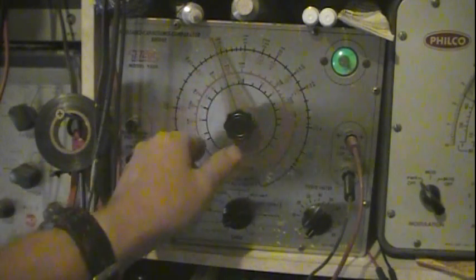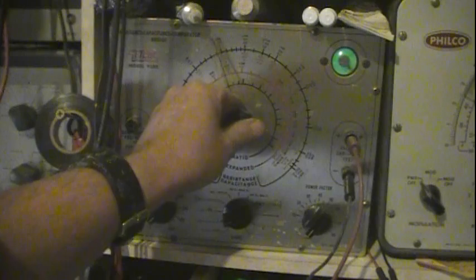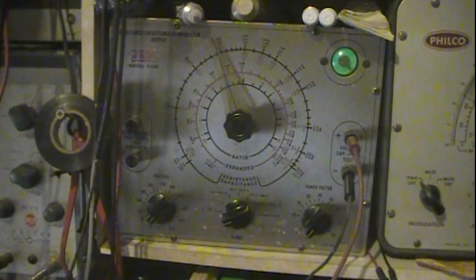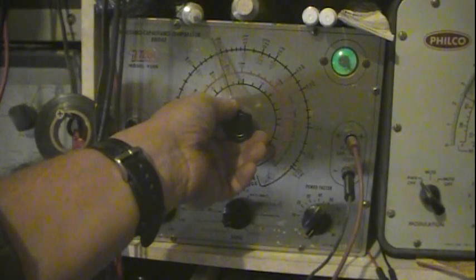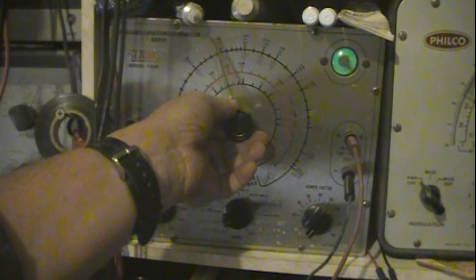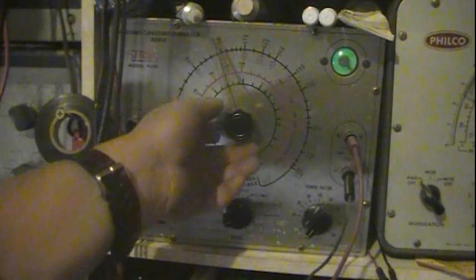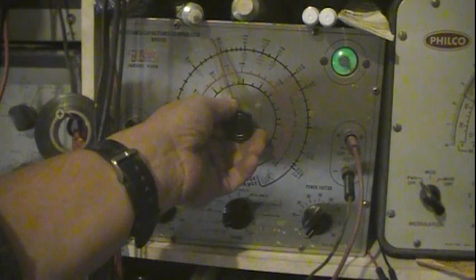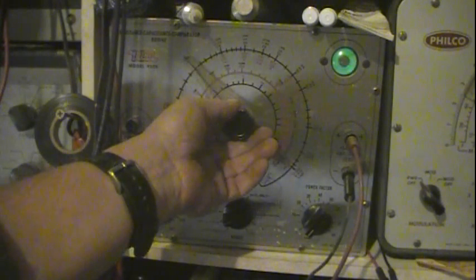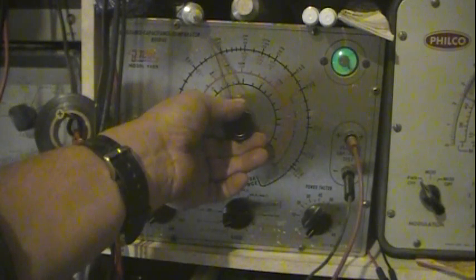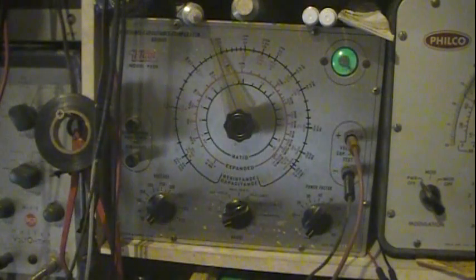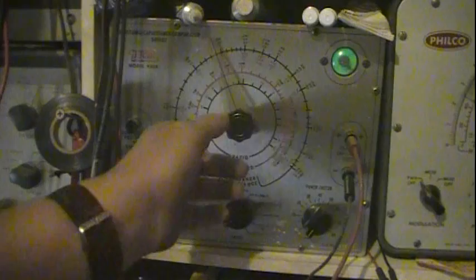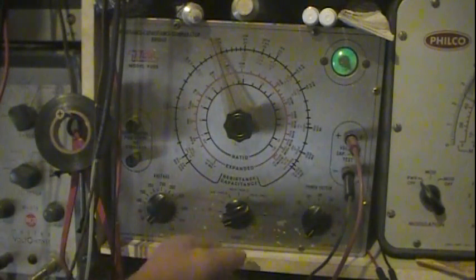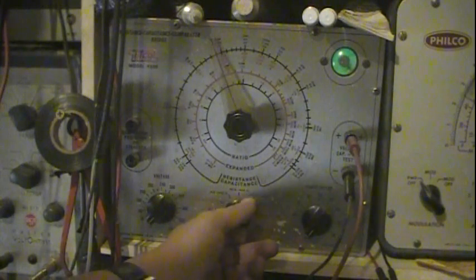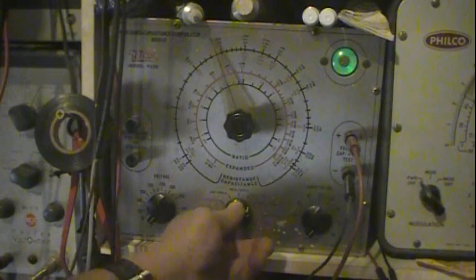It's not a real good eye opening. And that usually indicates that there's problems with the capacitor. It may be leaky, or the dielectric's not breaking down to the point where it will get leaky, but it's breaking down where the capacitance is not too good anymore, or the ends are getting moisture where the wires connect on and causing corrosion and high resistance there. But we're running about .014, excuse me, on that. So it's a little high, but probably well within its normal tolerance. We'll take it to the leakage test.